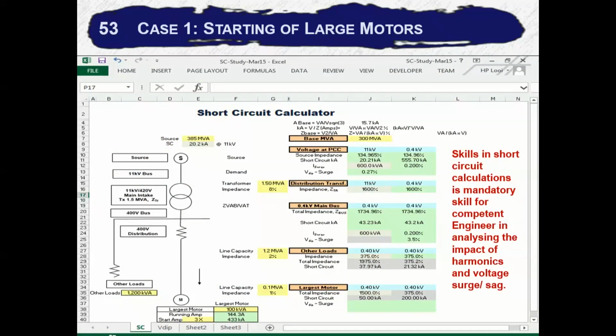Another industry which uses large motors is the oxygen plant, like I used to do for Air Products. Their motor is something like 1,000 horsepower. Now, a very strange fact is that in the building industry, aircon usually has 1,000 tons; you have three units of 1,000 tons. 1,000 tons is about 1,000 horsepower. Because aircon is designed by building engineers, all the aircon chillers are low voltage. But usually, as electrical engineers, instinctively, if we have any motor of more than, let's say, 100 horsepower, we will connect at either 6.6 kV or 11 kV.